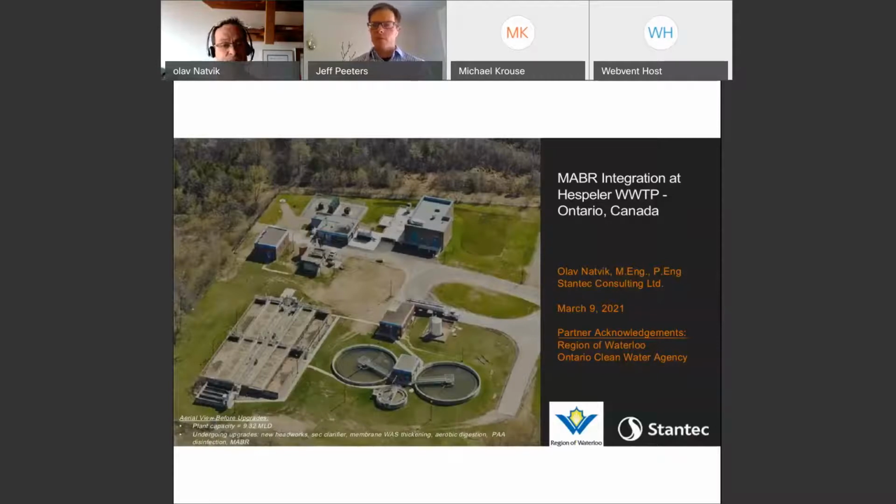The subject of my presentation today is the MABR integration at the Hespeler Wastewater Treatment Plant. The plant is located in the region of Waterloo, which is approximately an hour drive west of the city of Toronto. In terms of geography, it's at about 43 degrees north latitude. It experiences climate-wise a warm summer, but a cold traditional Canadian winter, you might say, where we see wastewater temps drop down to 10, 12 C. And in this particular case, this plant struggles and it loses nitrification when they see those low winter temperatures.